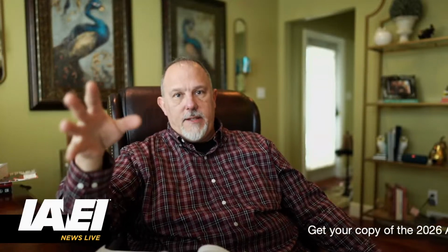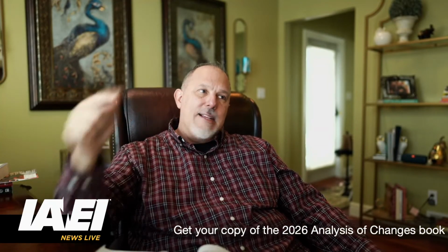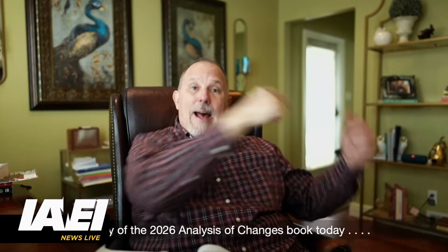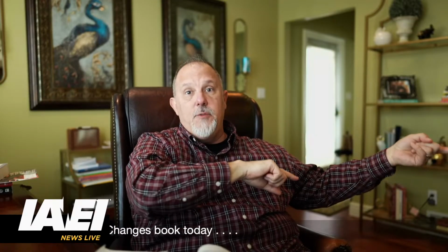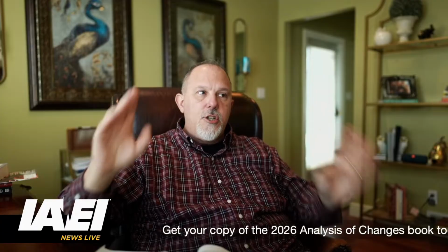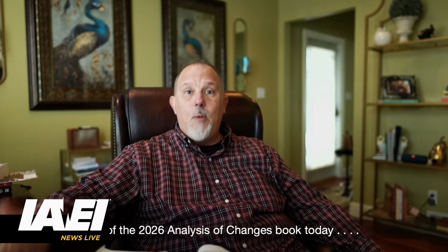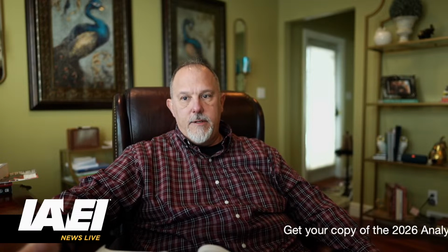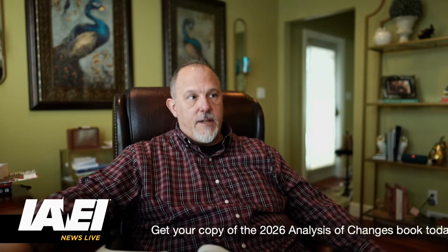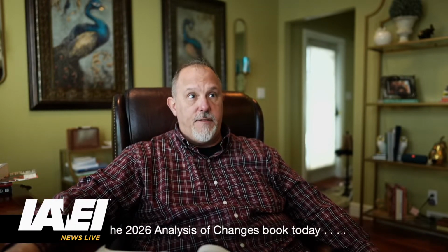So we did a couple things. We said it has to be outdoors. We went back to the 2020 language and basically reworded it to align with the style manual. And we made the assured equipment grounding program a requirement. If you're not going to put GFCI, then you want an assured equipment grounding program. It's not just permitted, it's required. That is a significant change, in my opinion, and a shift.